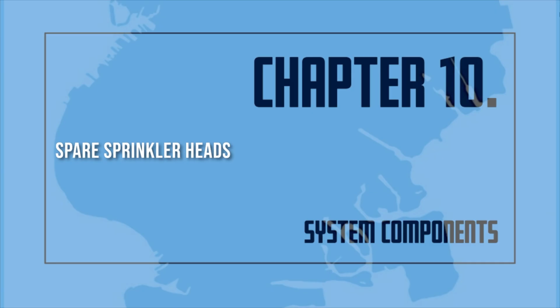After activation by fire, sprinklers in close proximity to the affected heads are recommended to be replaced. A stock of spare sprinklers, not less than 6, shall be kept on the premise where the temperature does not exceed 100 degrees Fahrenheit, and shall include all types and ratings installed in the protected facility and provided as follows. Under 300 sprinklers, 6 spares are required. For 301 to 1,000 sprinklers, 12 spares are required. If there are over 1,000 sprinklers, 24 spares are required.